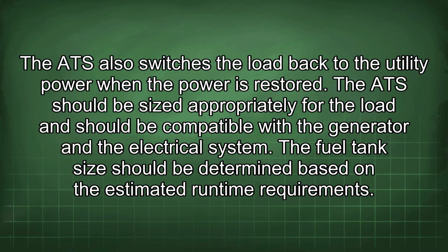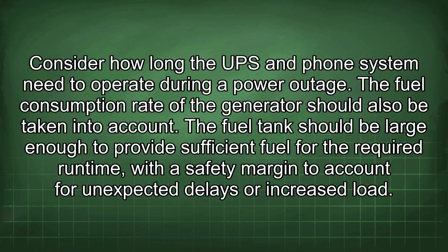The fuel tank size should be determined based on the estimated runtime requirements. Consider how long the UPS and phone system need to operate during a power outage. The fuel consumption rate of the generator should also be taken into account. The fuel tank should be large enough to provide sufficient fuel for the required runtime, with a safety margin to account for unexpected delays or increased load.